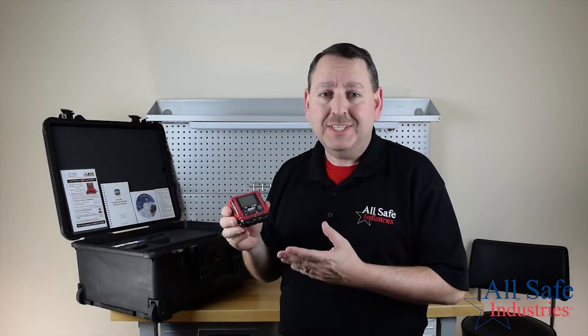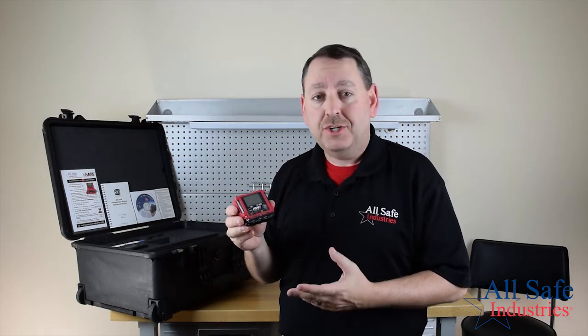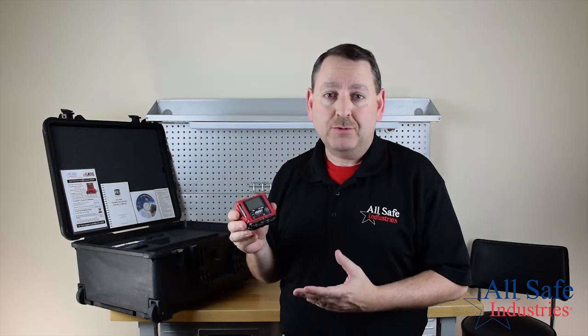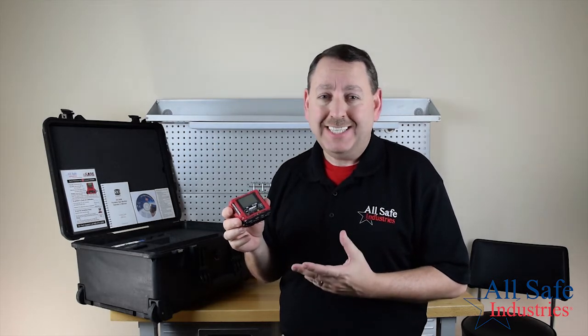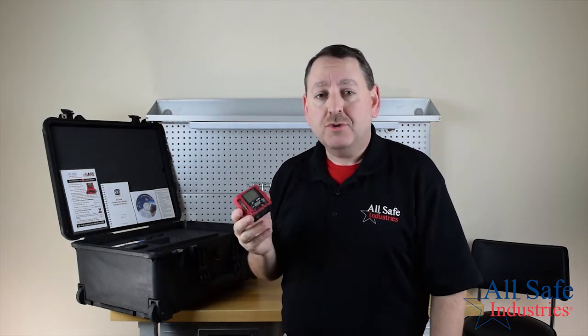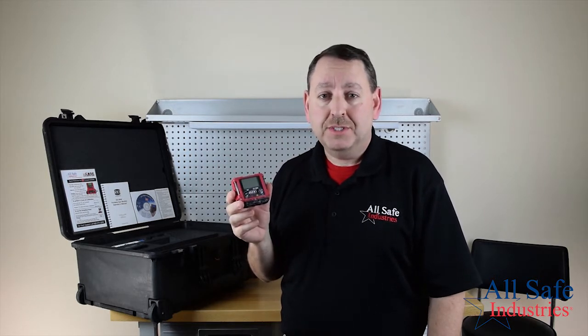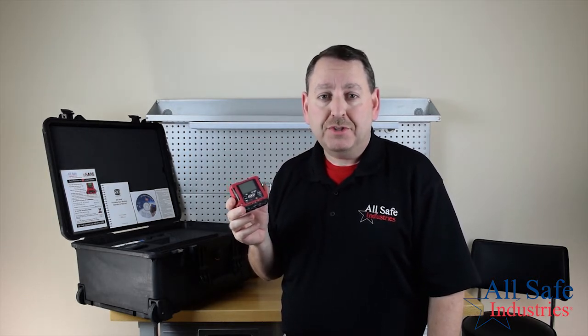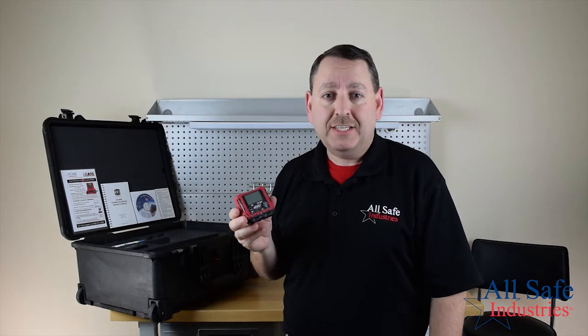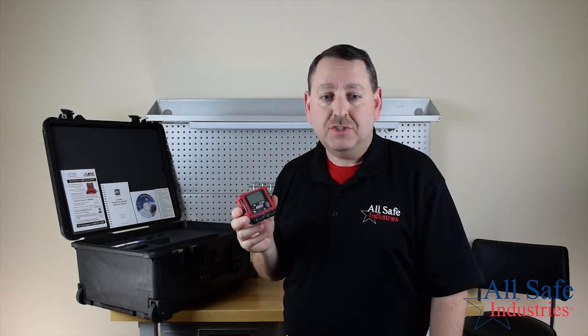I'm going to show you how to do the daily startup of the instrument, including a fresh air calibration and doing a bump check with your cal gas. And then I'm going to show you how easy this meter is to use. I'm also going to talk about calibration of the instrument. The factory recommends that you calibrate the meter at least once every 90 days. So I'm going to show you how to do that with the accessories that are in your kit.